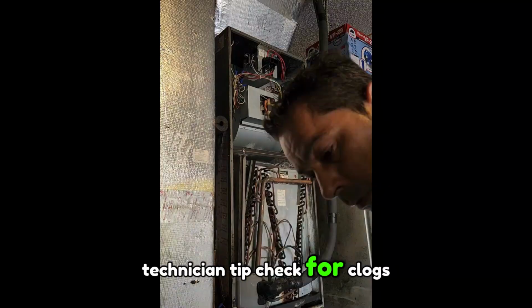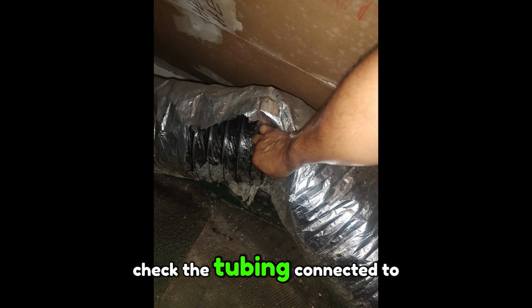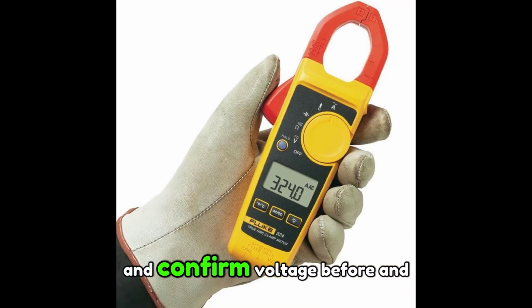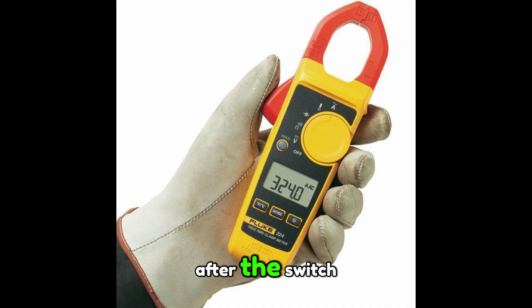Technician tip: check for clogs in the flue pipe, check the tubing connected to the pressure switch, and confirm voltage before and after the switch.